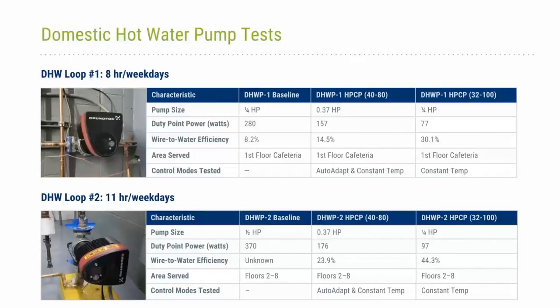And then the duty point power is essentially the power draw from the pump at the peak flow rate and peak differential pressure. So one thing that's interesting that you'll see here is, moving from the baseline pump to the high performance circulator pump, you were able to get over a 44% energy savings, even if the pump were to run at 100% speed all the time. So very significant energy savings for this. And you see the low wire to water efficiencies, which is just a metric of pump efficiency multiplied by motor efficiency. Again, the reason those are low is because it's higher differential pressure or higher head pressure combined with low flow rates.